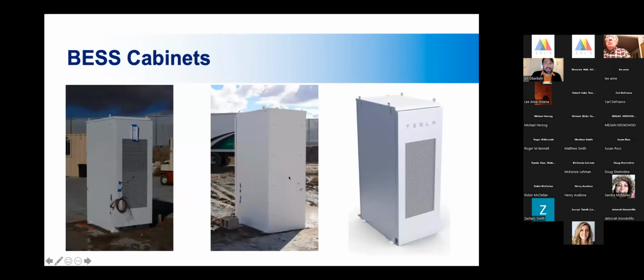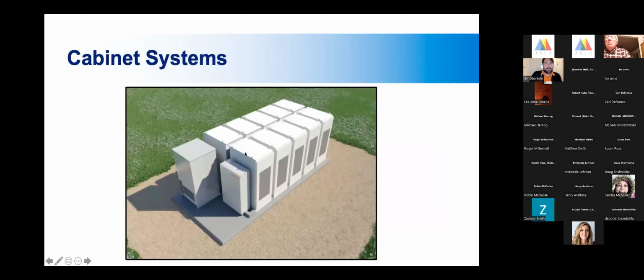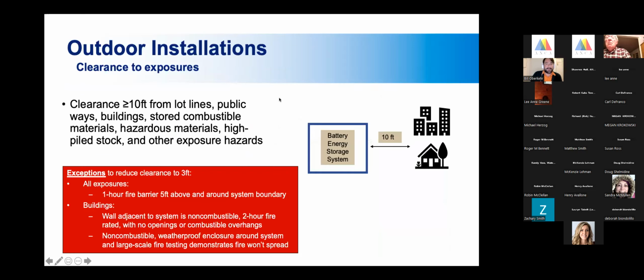This is what energy storage cabinets look like. These again are about the size of a refrigerator, more or less. This is a cabinet system. Surprise, surprise, it's a bunch of cabinets right next to each other. Outdoor installations. So this is a good one because outdoor remote installations need to be 100 feet away from everything. Every energy storage system needs to be at least 10 feet away from everything. So you can't have an outdoor near exposure installation that has, say, a building within 10 feet or a lot line or anything else. That's essentially what this is saying.